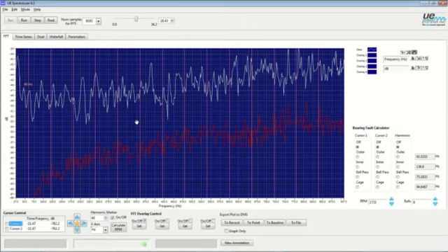It still doesn't tell me the type of fault. So for this, what I'm suspecting there is an arcing and or a tracking event. It's a very common fault, and you can hear these things going on as well as visualize them. Another thing that happens on these higher voltages, we all know about corona, and the two different types of corona being nuisance or normal corona, and then we have destructive corona.